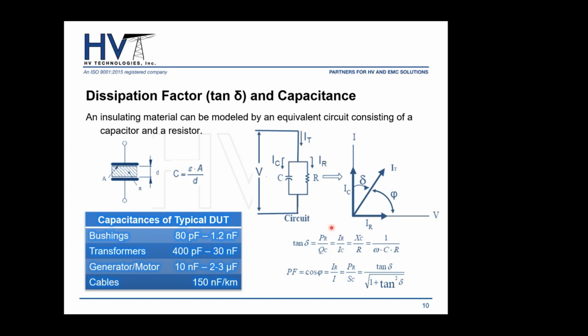Now, if you see the graph here on the right hand side, although this is exaggerated just for clarity, this is how the insulation behaves on a vector diagram. You'll have your capacitive current, which always leads your voltage signal by 90 degrees. And then you'll have any resistive current, which will be in phase with your voltage. As this resistive current increases, it pushes your total current away from the y-axis. So you have essentially a generation of an angle between your capacitive current and your total current. This angle is known as the tangent.